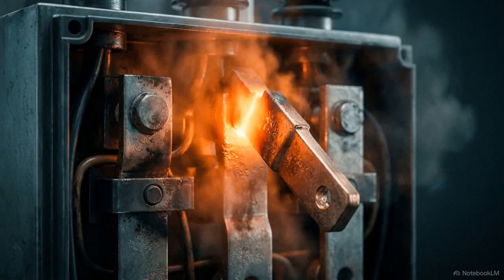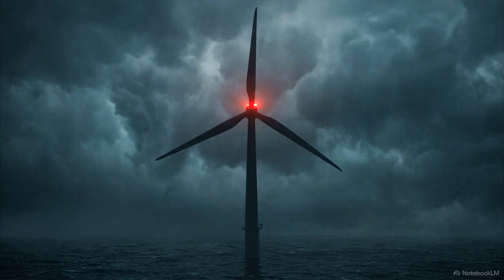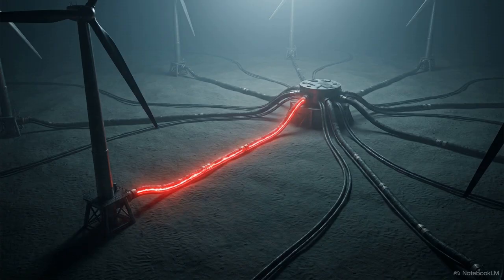Because of that single remaining point of contact, the turbine is now stranded in an electrical limbo. It is no longer fully connected to the grid, but it is not completely isolated either. That tiny mechanical glitch pushes the entire electrical system out of equilibrium. It silently arms an invisible trap, hidden inside the grid itself. This animated diagram shows a cross-section of a long submarine export cable.